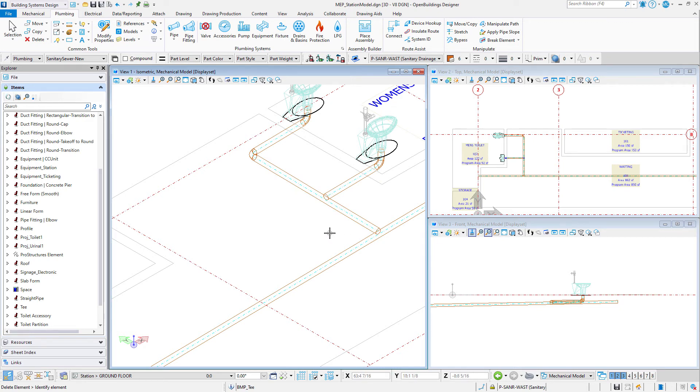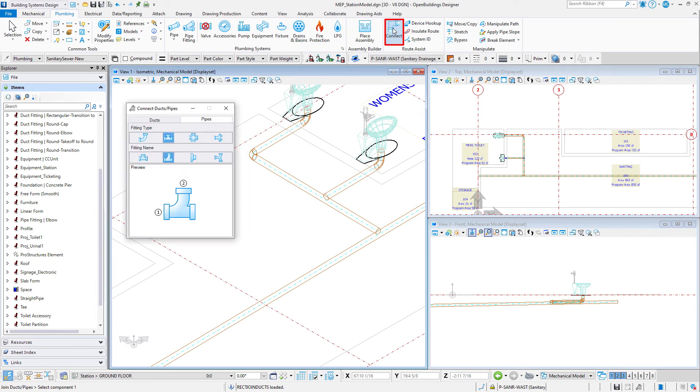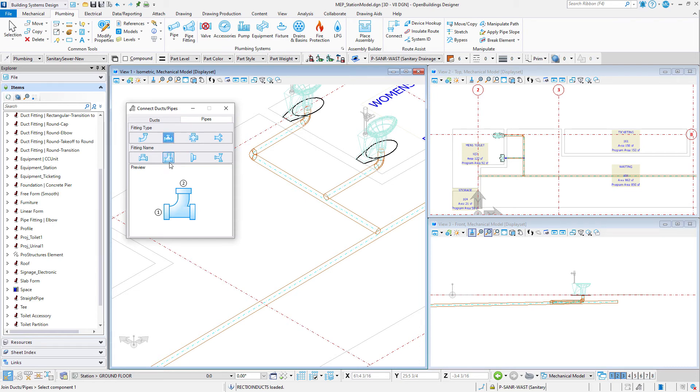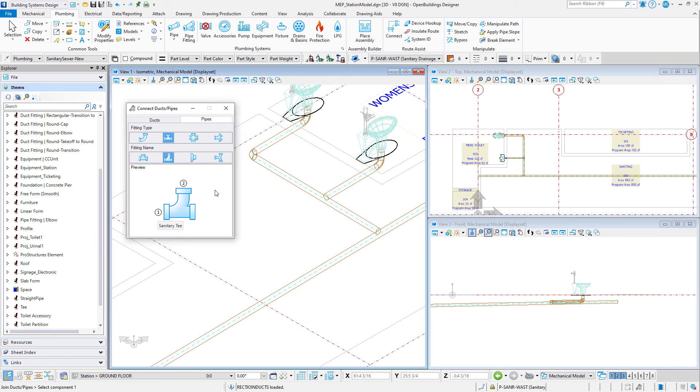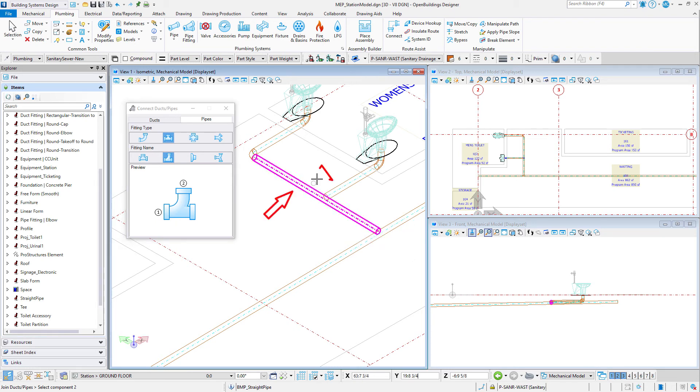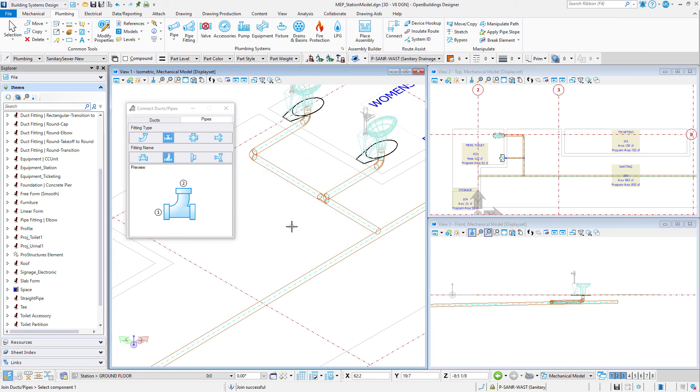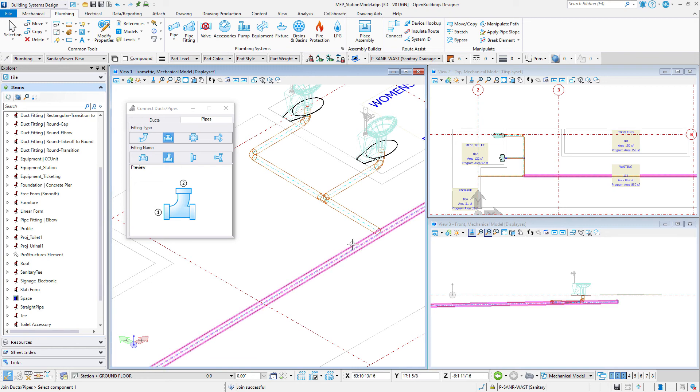Select the Connect tool from the Route Assist group on the plumbing ribbon. In the Connect Duct Pipes dialog, select the Pipes tab. Set the fitting type to Join with T and the fitting name to Sanitary T. Note that the numbers 1, 2, and 3 in the preview window represent the order in which you need to select the pipes to be connected. Select the first pipe, then select the second pipe. A Y connection is added correctly oriented based on the slope of the pipes. Repeat for additional Y connections.